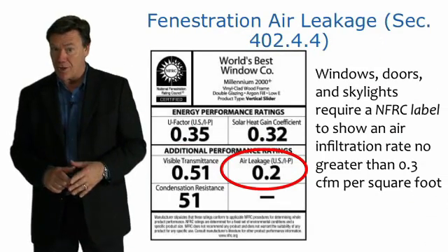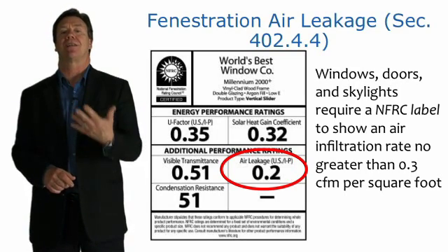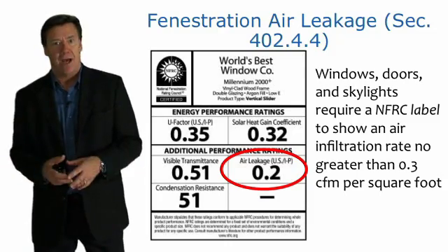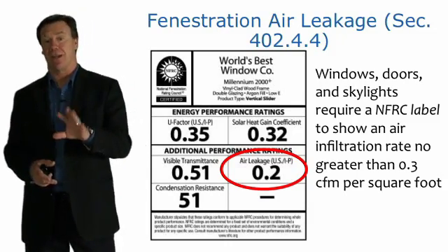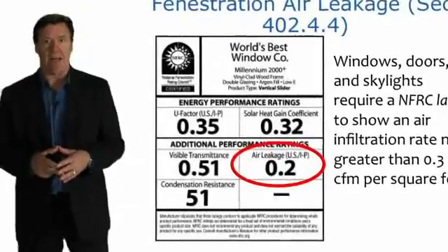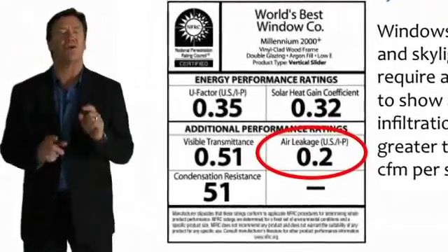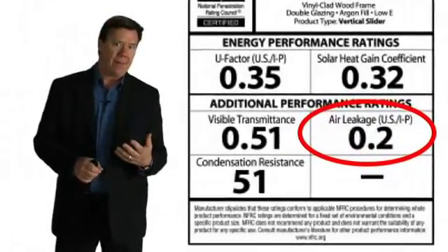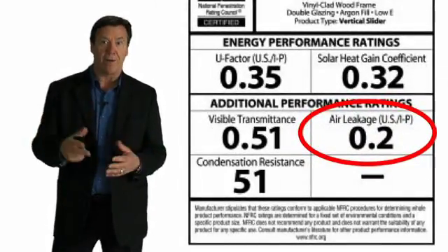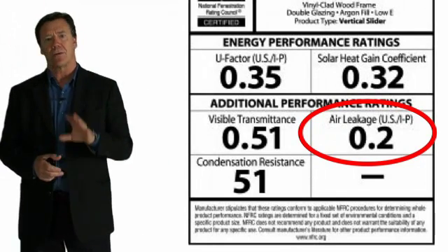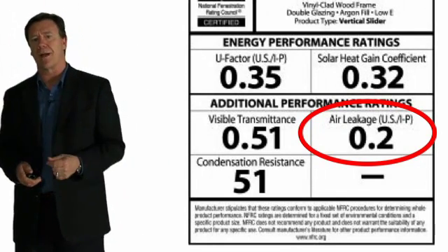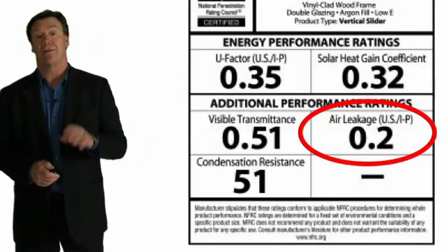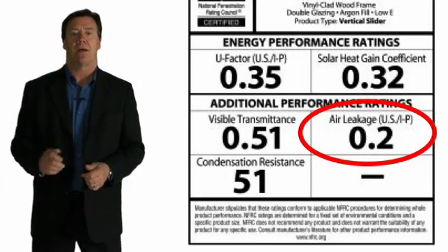Regarding the NFRC label on fenestration, in addition to heat loss and heat gain, another important component is air leakage. This window, for example, has an air leakage of 0.2 CFM per square foot, and the code requirement is no more than 0.3 CFM per square foot, so this window qualifies. This is something to look for when selecting windows and during building inspections.